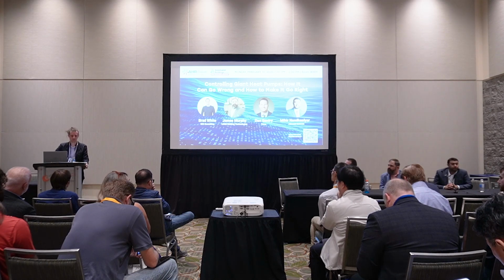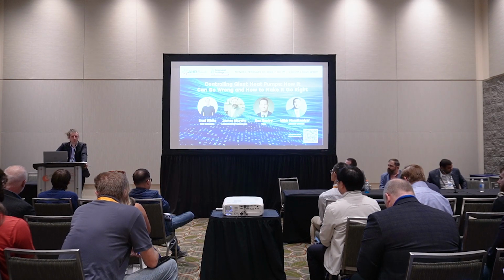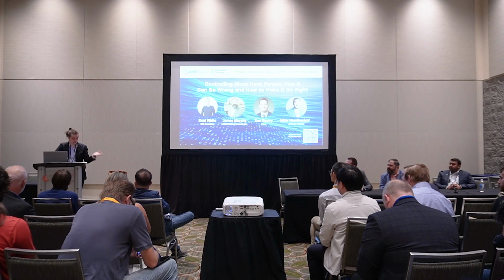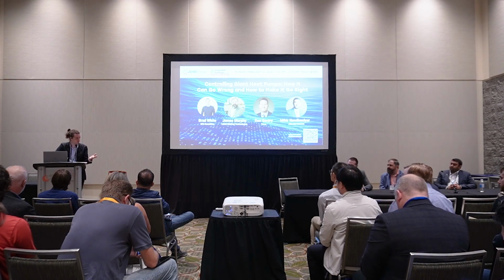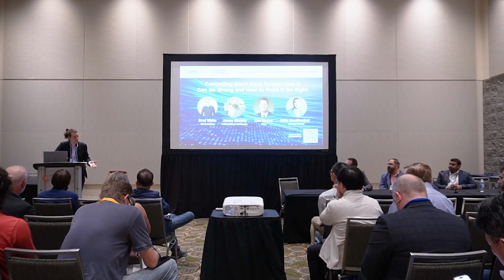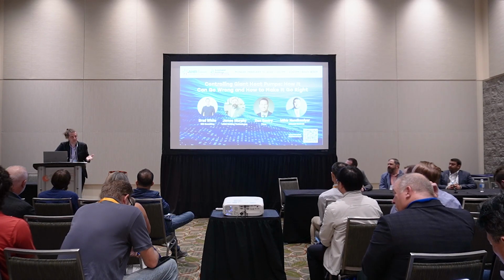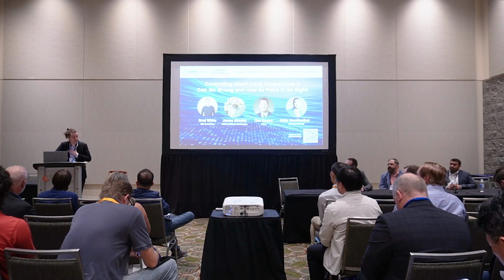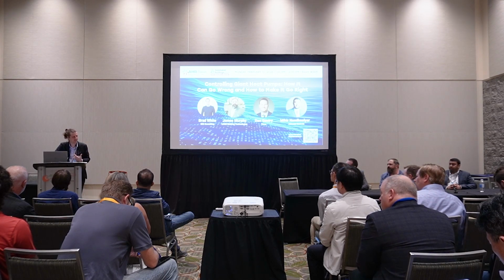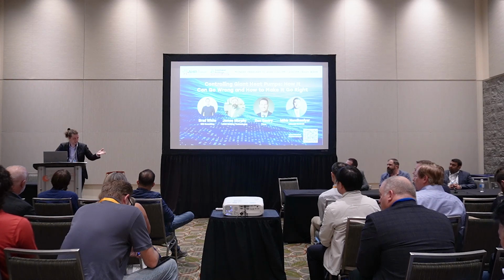That jives with my experience as well. One thing I often boil it down to is that heat pumps are not boilers. A lot of the things you can get away with doing with boilers, like variable flow and aggressive temperature resets, just don't work with a heat pump. It's a fundamentally different piece of technology. I'll speak as an engineer, but I feel like the engineering community is just starting to realize that, almost thinking we can really optimize this thing the same way we optimize boilers, and then not realizing.